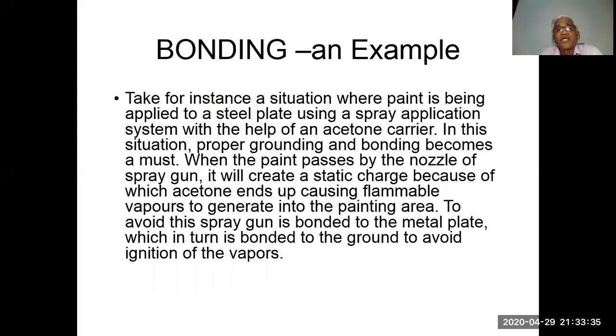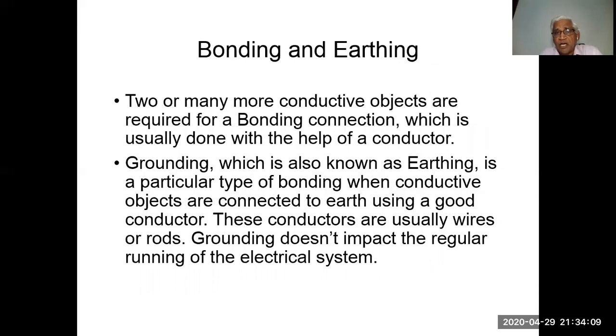Bonding example: take for instance a situation where paint is being applied to a steel plate using a spray application system with the help of an acetone carrier. In this situation, proper grounding and bonding becomes a must. When the paint passes by the nozzle of the spray gun, it creates a static charge, because of which acetone ends up causing flammable vapors to generate in the painting area. To avoid this, the spray gun is bonded to the metal plate, which in turn is bonded to the ground, to avoid ignition of the vapors. Bonding and earthing.